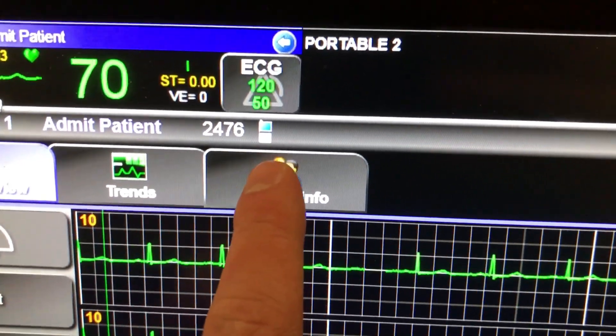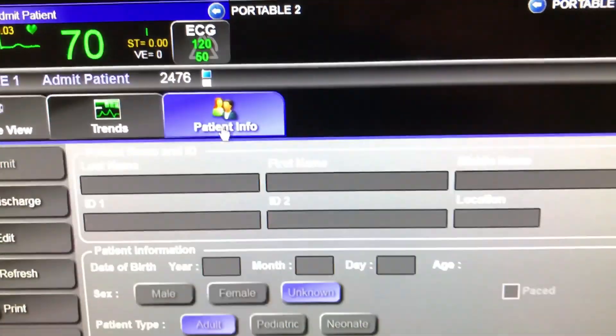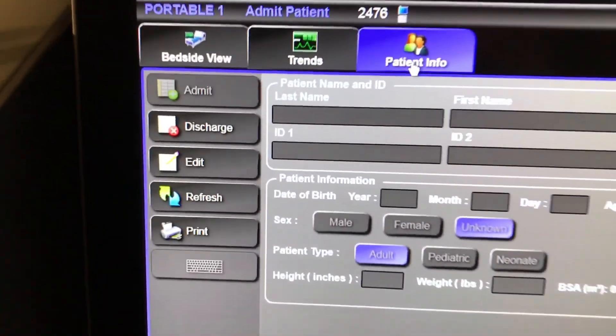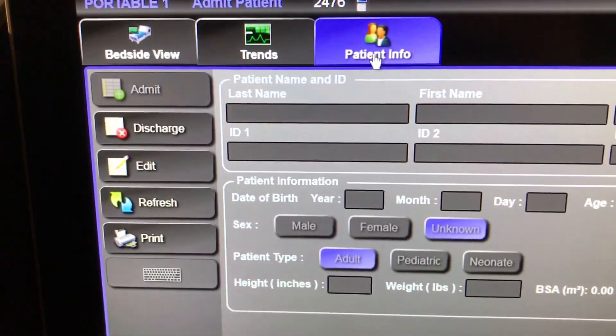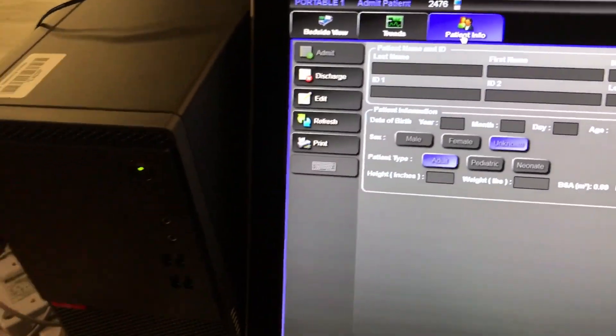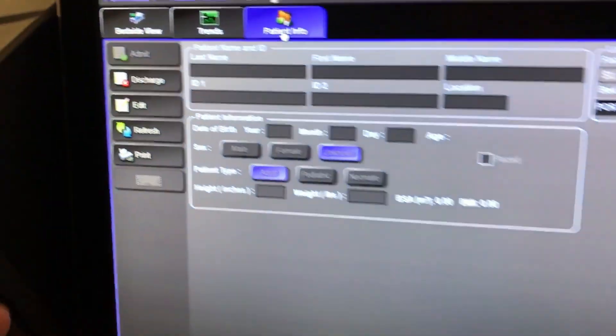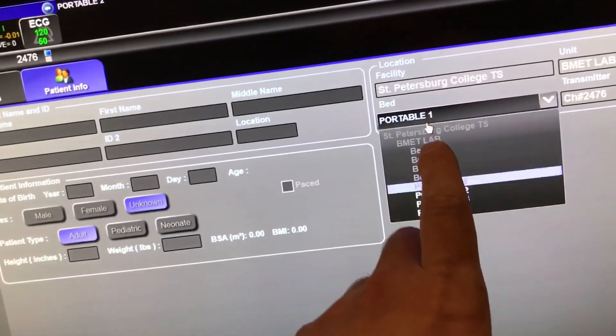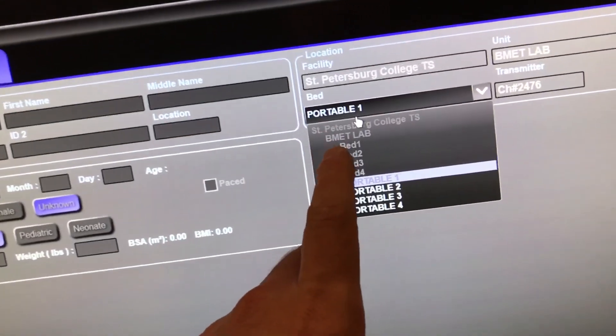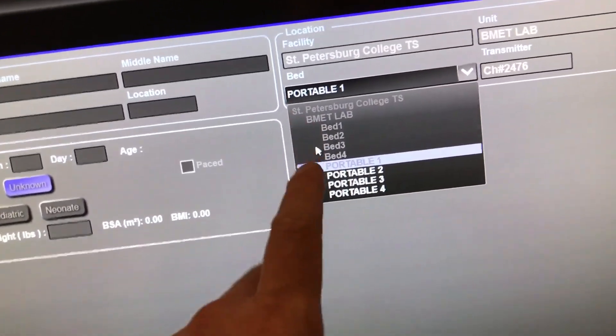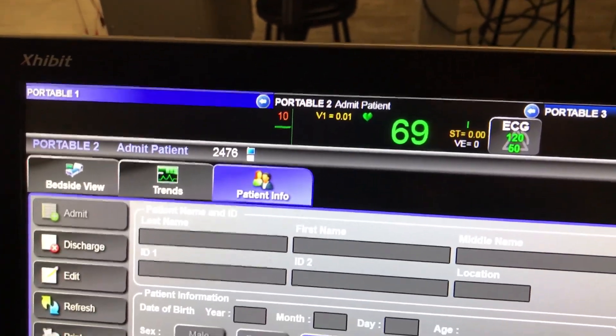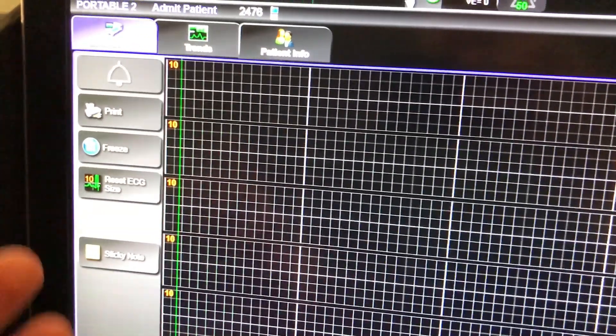But when you open this up, it'll show you three tabs at the top. Patient info is the one you're looking for. This is also where you go to tune the channel. But it's also where you go to make changes to that patient or admit or discharge them. To fully remove the transmitter unit, the only way I've found really to do it is to fully discharge the patient. I think what you could probably do is if you had another ECG setup, you could transfer them to another bed. Because from here, you can transfer this patient from one screen to another.